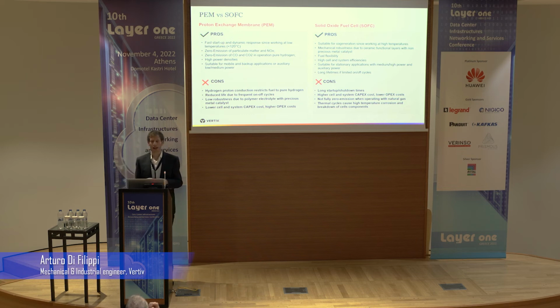The advantage of the other fuel cells is that their efficiency is very high, which is why they need to be used for prime power. They could take hours to heat up, but if you use them as prime power, they can last a very long time. Used with high efficiency, they can be more efficient than diesel generators, and can be used in data centers as a primary source of power.